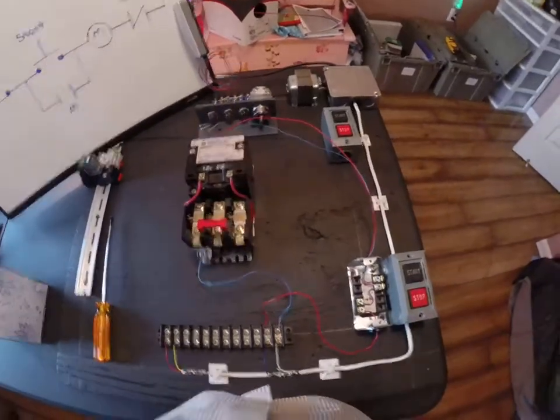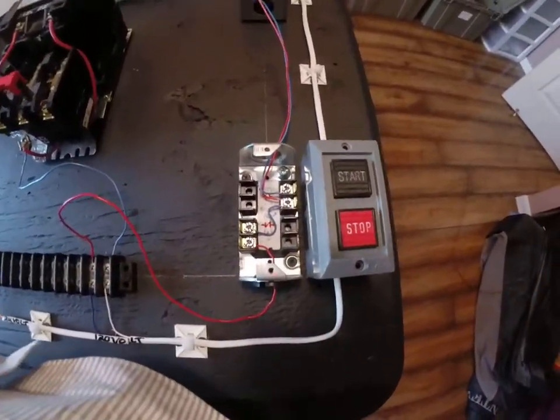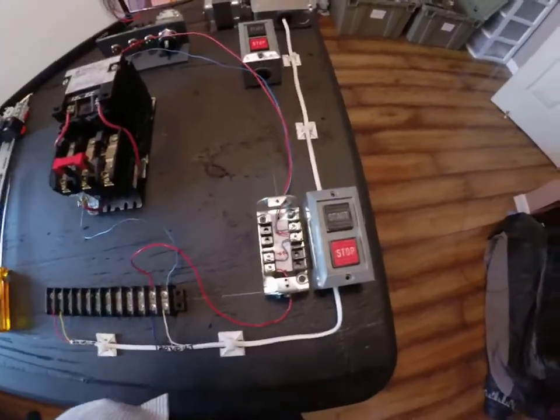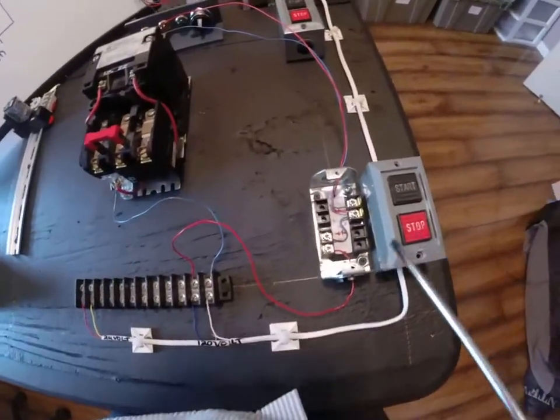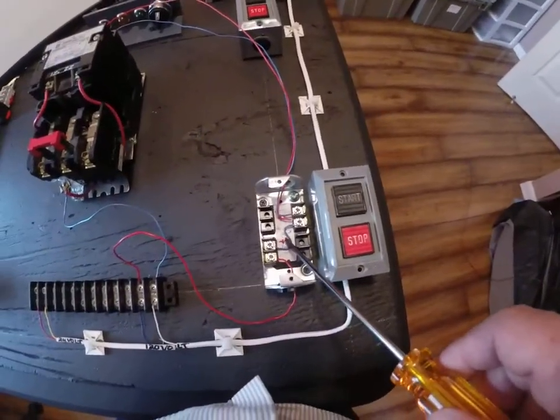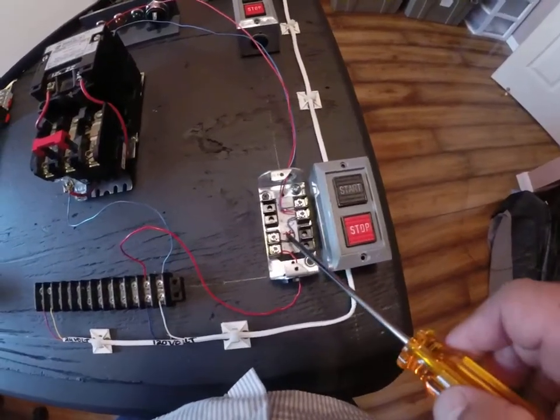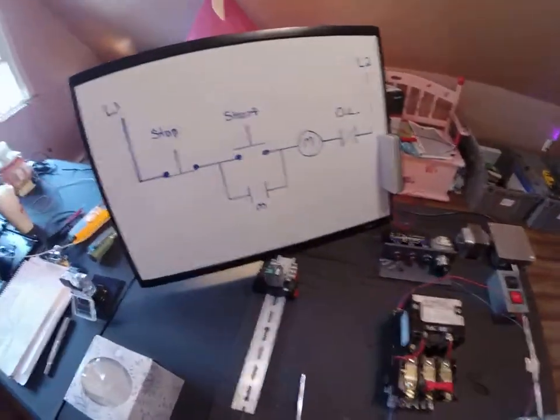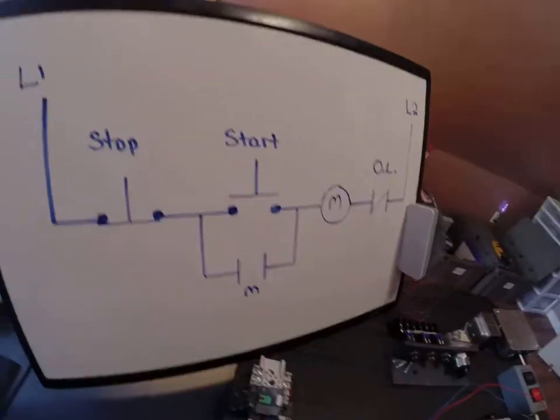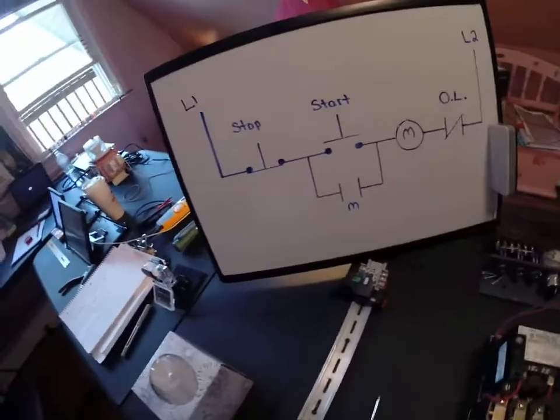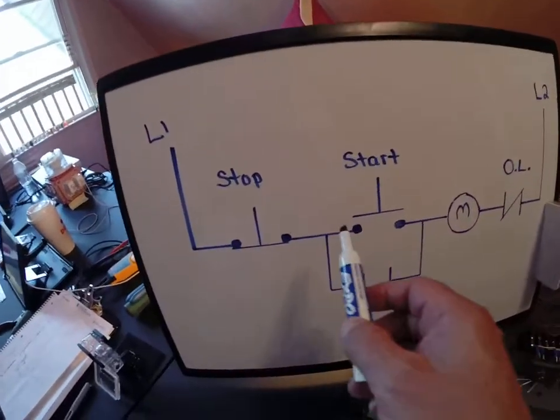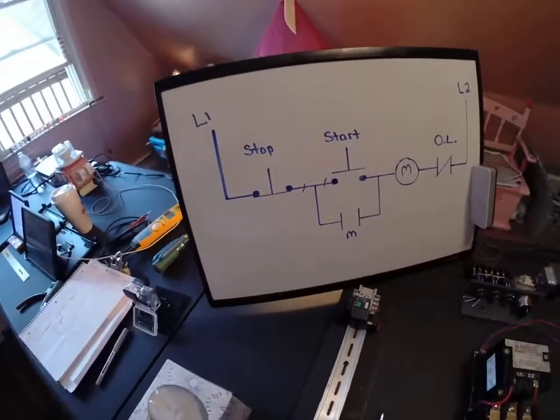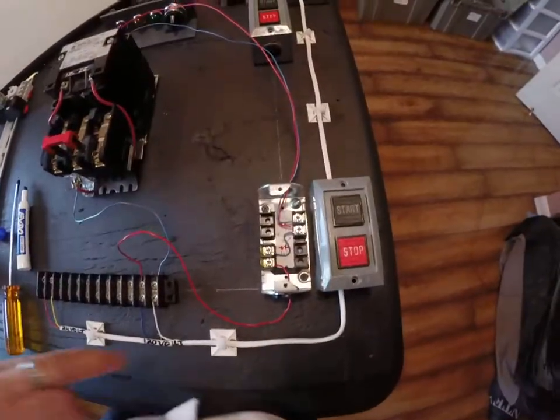We have a stop-start station and it's the first time we've actually had the stop and start wired in the same enclosure. One thing I'd like you to take note of is there's a jumper between the second screw of the stop and the first screw of the start. If I show you this on the whiteboard, that jumper is actually this cable right there.